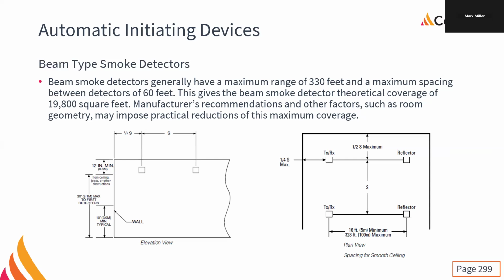Now, if we've got a 100-meter long room, it's probably going to be pretty wide as well. So we're not going to be putting in just one. We're going to be putting in more. So we could have two or three or four going across the width of the room. And if it's a really tall room, we might have to double stack them. We might have to put two different levels of beam detectors in. Manufacturers have all the say on this one, right? Because they've designed their system, they've done all the testing, they know exactly where it needs to be.